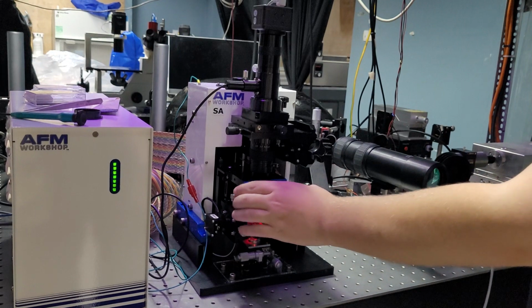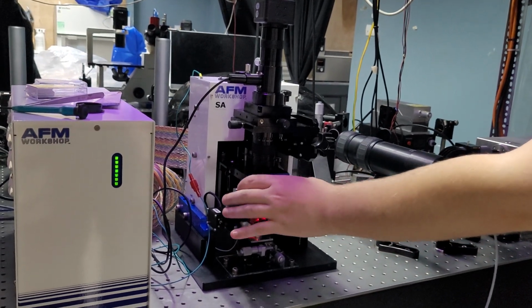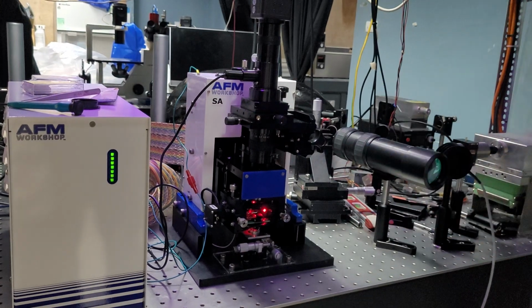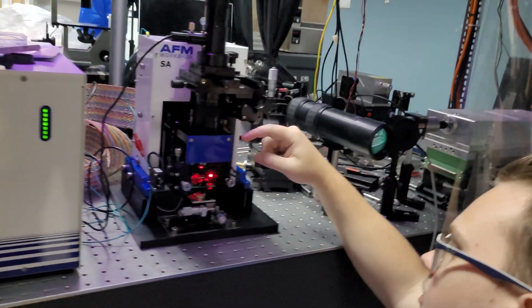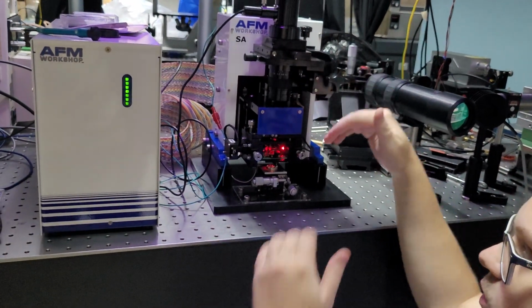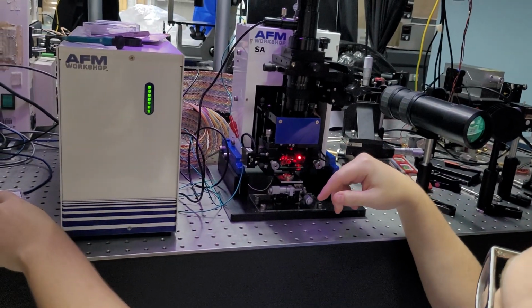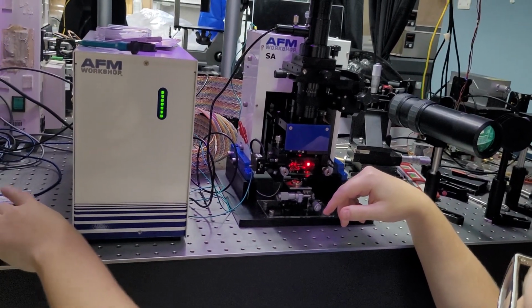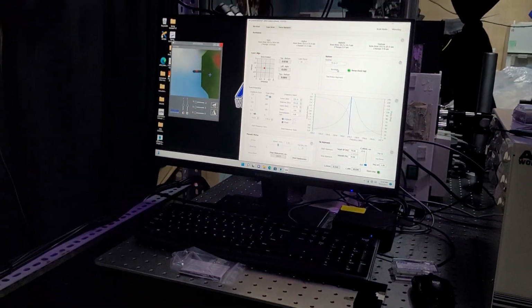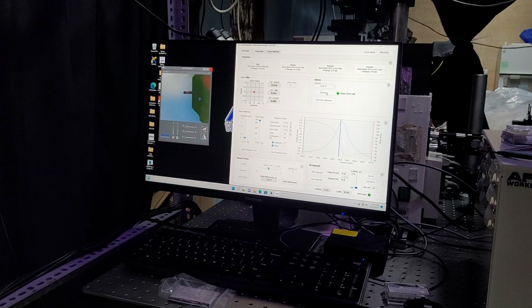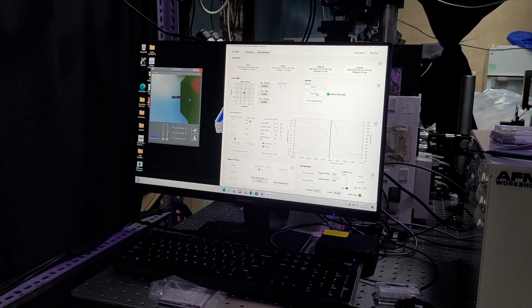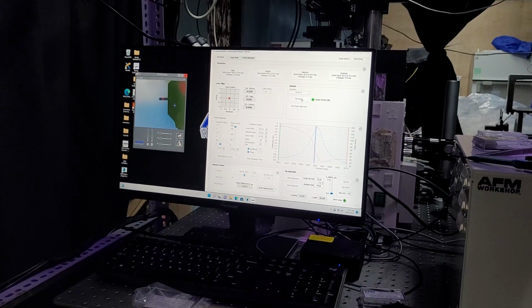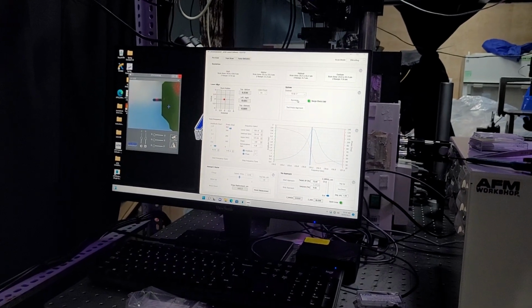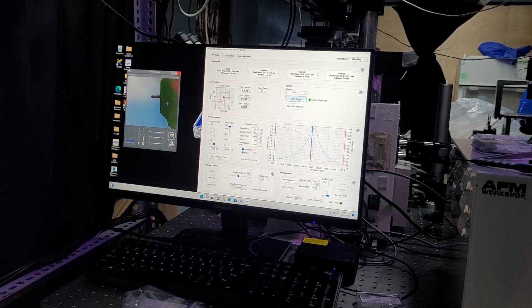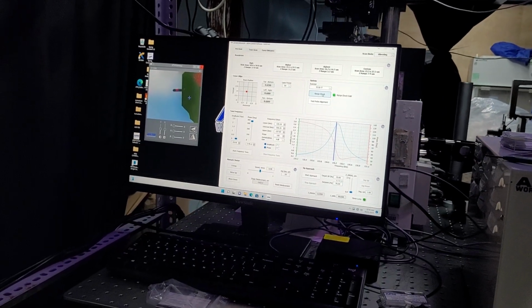Going on a little bit further down, you'll see this blue plate here. This is just covering the scanners, the XY scanner behind it. So behind this, there are X and Y piezos that will cause the motion, that if I go ahead and press range check here, you can see that the tip is moving. And what that's doing is it's just pushing in X and then pushing in Y. Which it still looks like that's not totally straight.